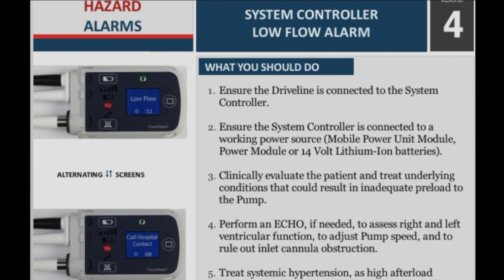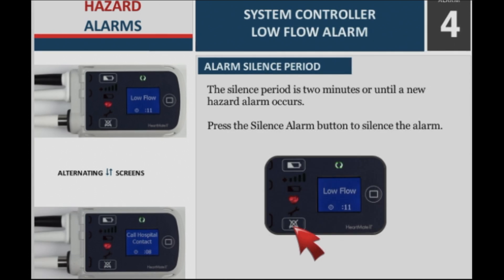Step 4: Perform an echo, if needed, to assess right and left ventricular function, to adjust pump speed, and to rule out inlet cannula obstruction. Step 5: Treat systemic high afterload. Alarm silence period: The silence period is 2 minutes or until a new hazard alarm occurs. Press the silence alarm button to silence the alarm.